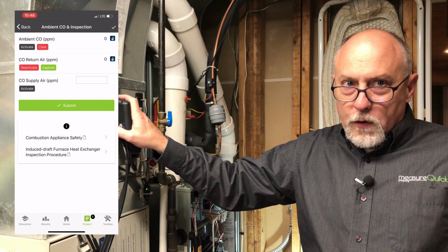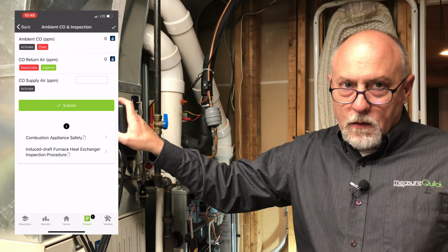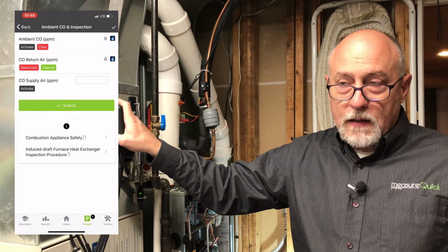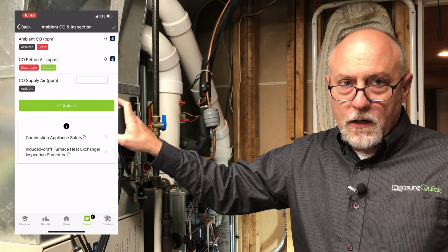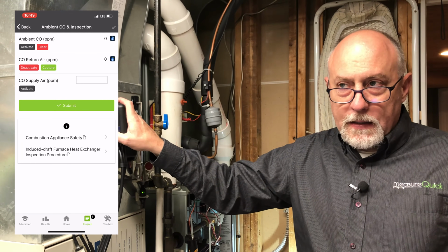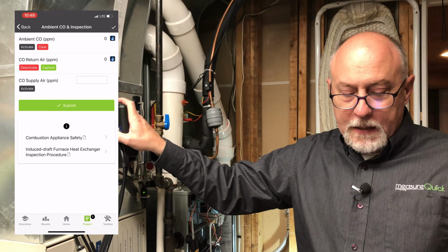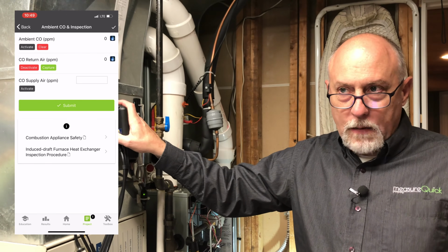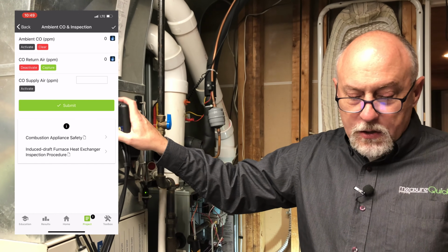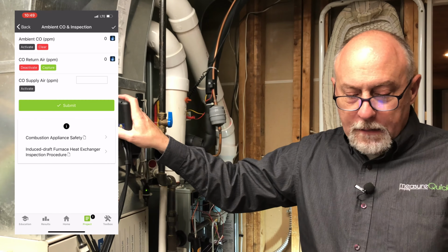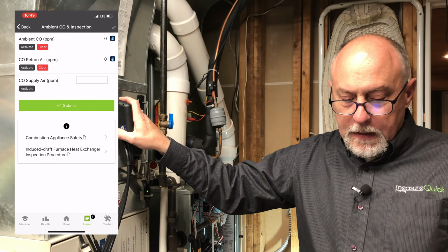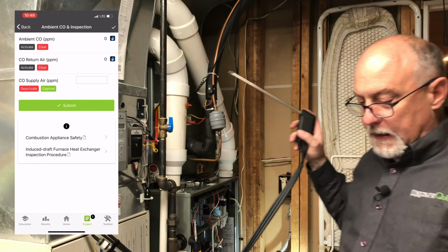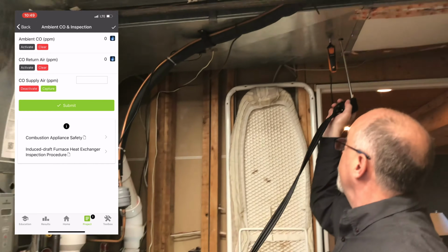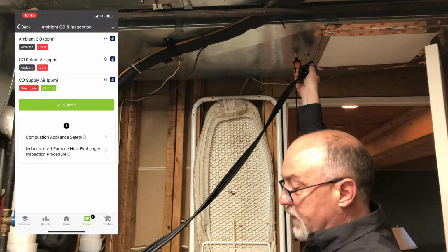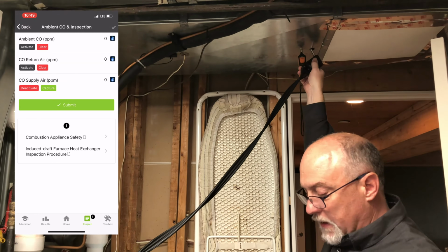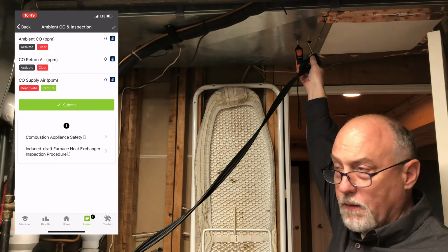Well, if you're in California, you've got a lot of attached garages, and you can have ductwork run through a garage. You can have other areas that produce CO, and you can pick up CO in a duct where you may not pick it up necessarily right where you're standing. So again, I have no CO in the return air. I'm going to hit capture on that, and I'm going to activate it again, and move it up to supply air here. We're going to give this a good minute or so in the supply air to make sure we're not picking up any CO in the supply.